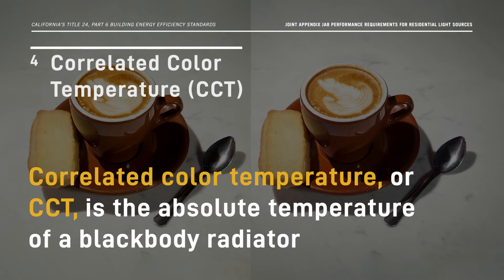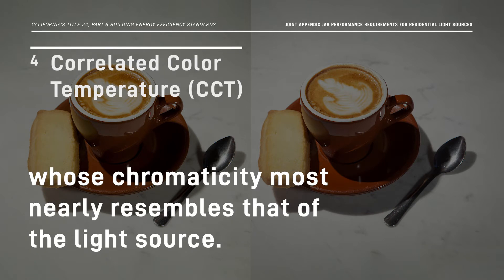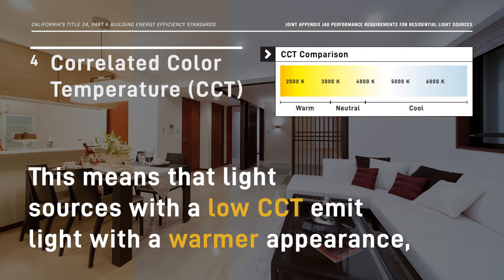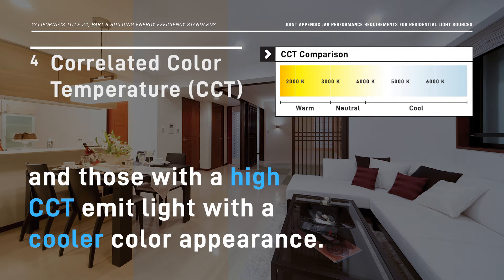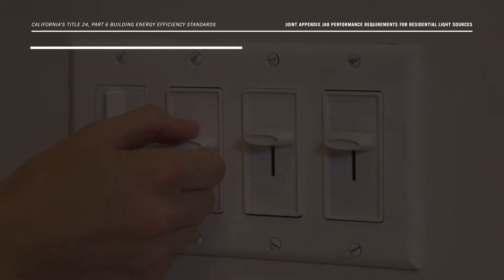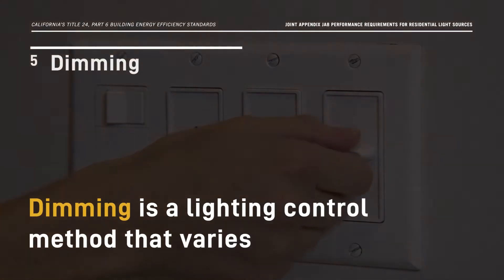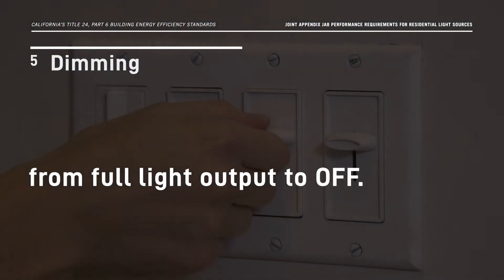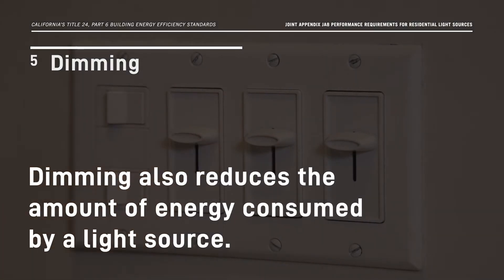Correlated color temperature, or CCT, is the absolute temperature of a blackbody radiator whose chromaticity most nearly resembles that of the light source. Light sources with a low CCT emit light with a warmer appearance, and those with a high CCT emit light with a cooler color appearance. Dimming is a lighting control method that varies the light output of a source from full light output to off, and also reduces the amount of energy consumed by a light source.